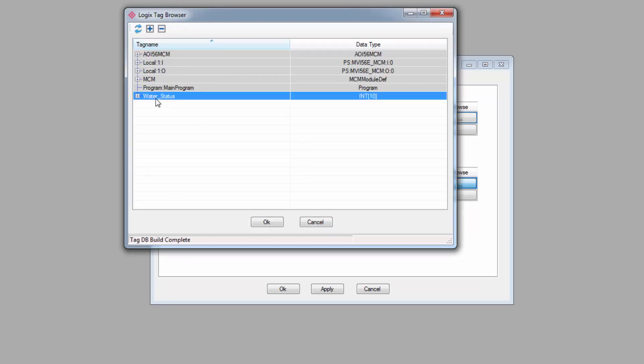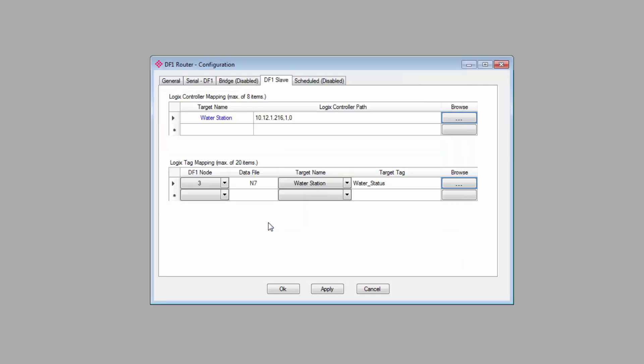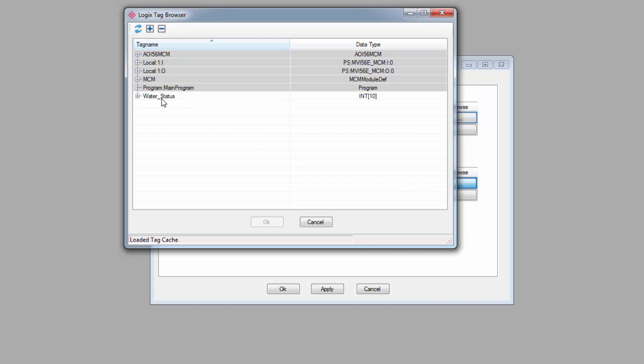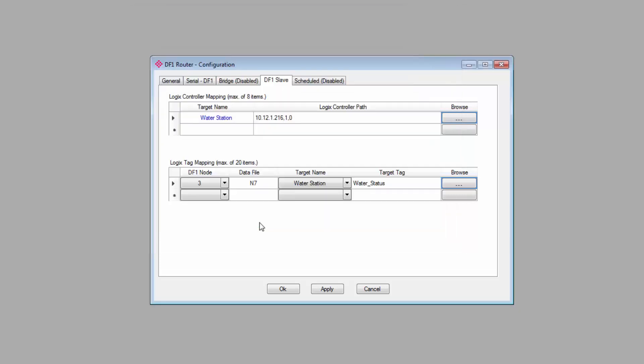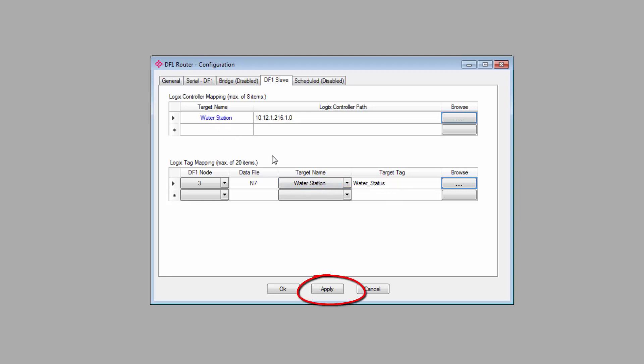Because no size is specified, you'll need to make sure that the array is big enough to satisfy the DF1 message size. Furthermore, the data type for the array must match the data type for the data table. So if a request N7 means the master on the DF1 network for node 3 wants to read data file N7, the data will come from the water status tag in the water station controller at this location. And that should do it.